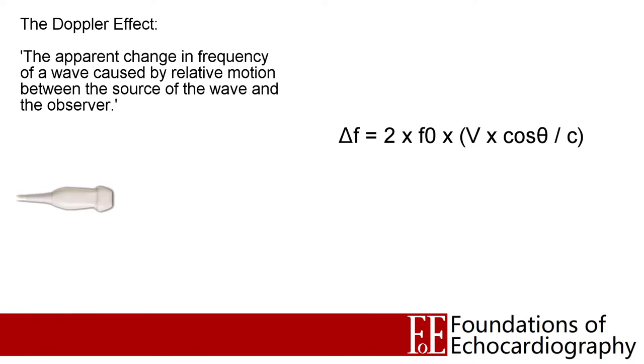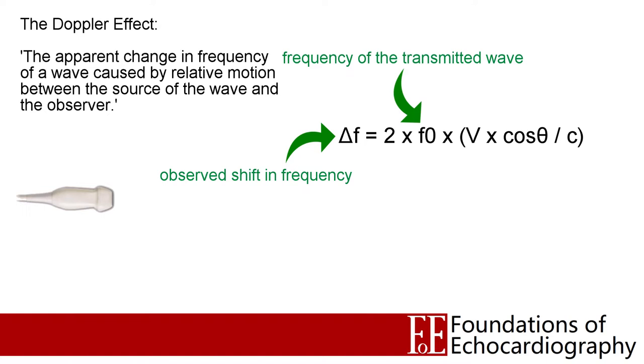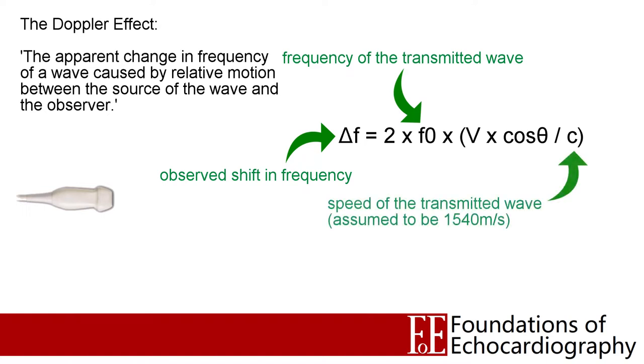Let's break this equation down to help us understand it. F0 is the frequency of the transmitted wave — that is the frequency that the ultrasound probe initially generated, and of course the software knows this. Delta F is the observed shift in frequency — that is the difference between the measured returning frequency and the known transmitted frequency, and using some clever maths the ultrasound machine can work this out. C is the speed at which the ultrasound wave was travelling. We make an assumption of an average speed and use 1540 metres per second in this equation.